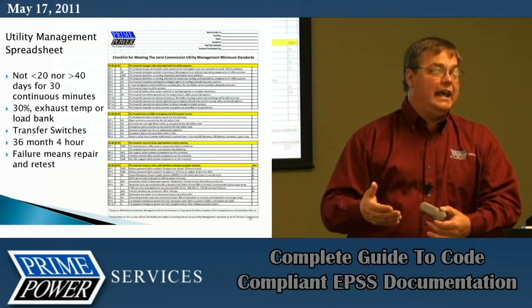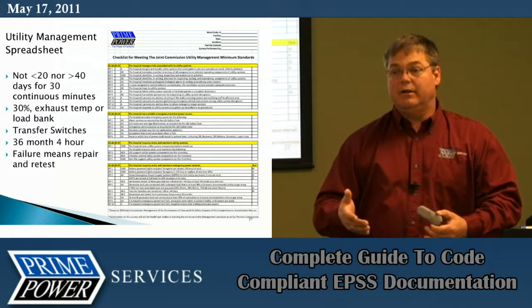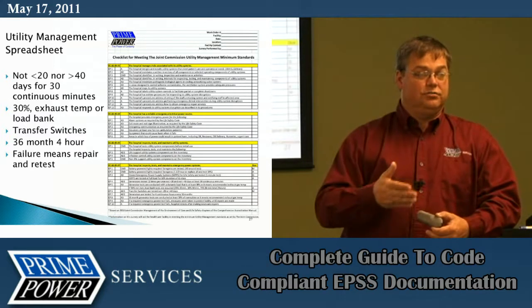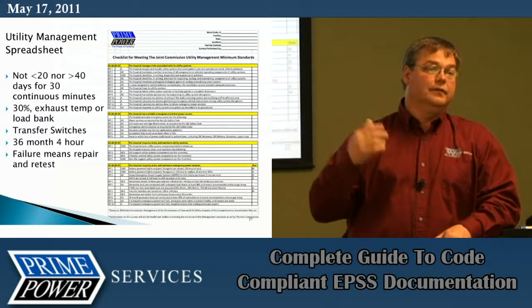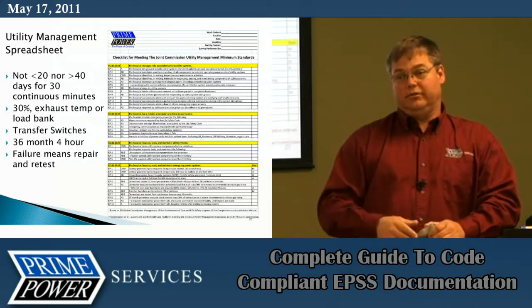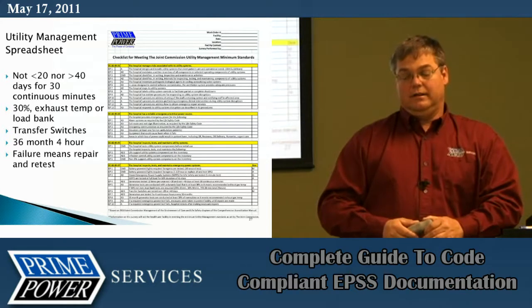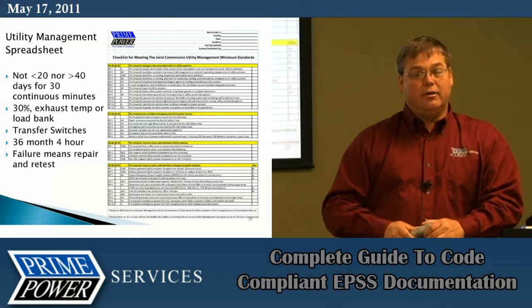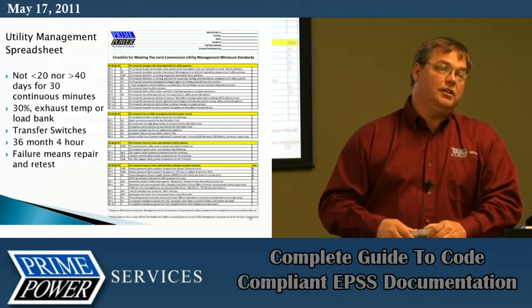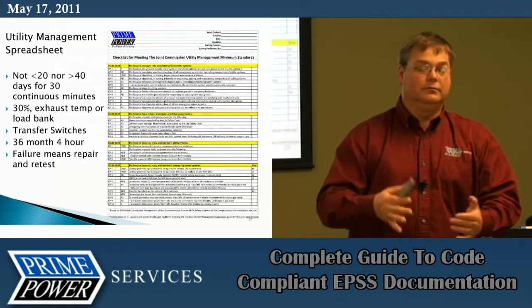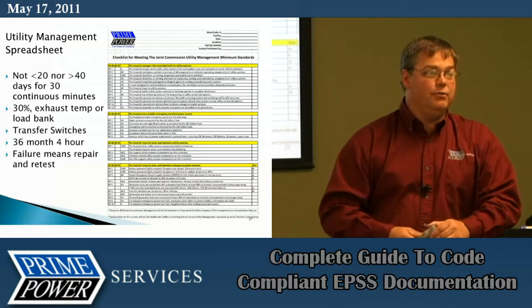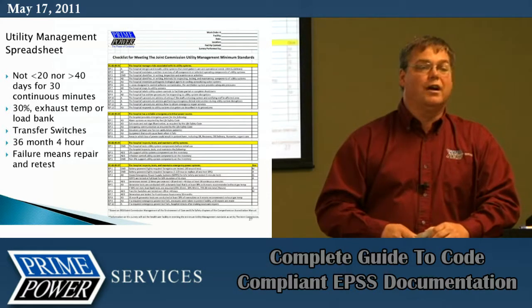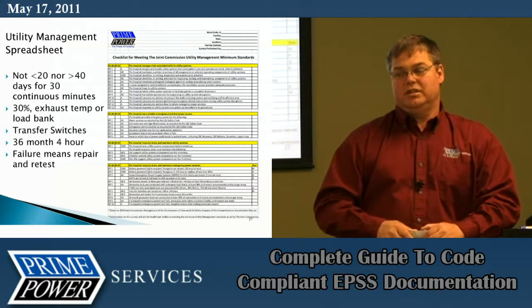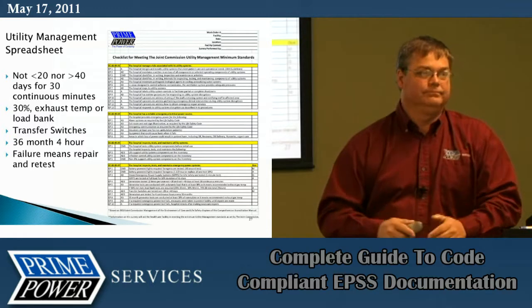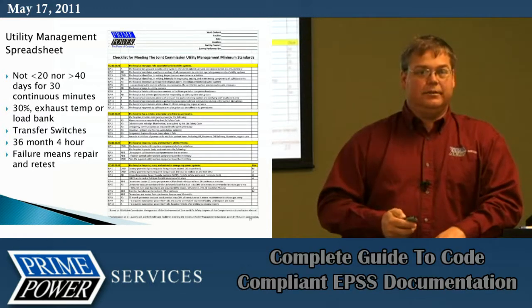There's no set guidelines on how often you must do that. My recommendation is just go all the way through the end and start again. Some of you may have more than 12 transfer switches. All right, that means if you just do a standard rotation, you're not starting that generator with that switch annually. That's your call for you to decide if you want to do that or not. There is no code requirement to do that. But you're not truly testing the switch if you don't. All right? Comment, questions on that?